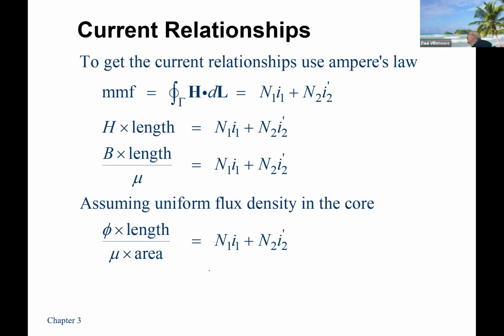So let's do a little bit of current. Go ahead. Will the temperature change if the transformer is used in reverse? It does not change, because the primary is now the secondary and the secondary is now the primary. But it's still the same basic design, right? It still has the same number of windings. The way you get a higher or lower voltage is you just change the number of turns on the winding. In the lower voltage winding, you have more current, but you also have bigger conductors. So your I squared R losses should be about the same. Make sense?